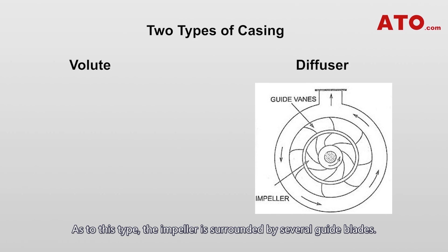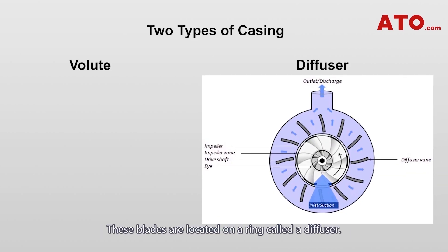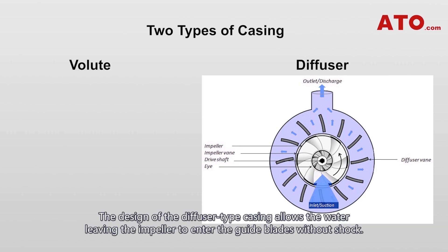In the diffuser type casing, the impeller is surrounded by several guide blades. These blades are located on a ring called a diffuser. The design of the diffuser type casing allows the water leaving the impeller to enter the guide blades without shock.